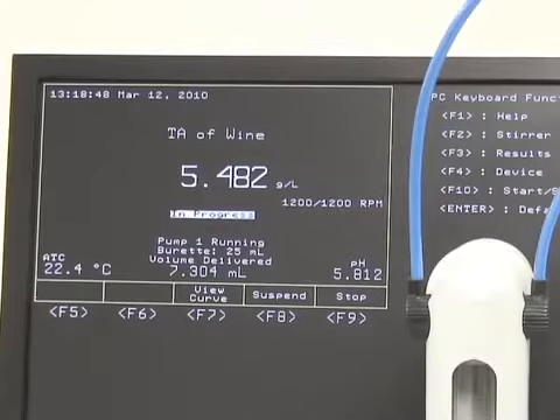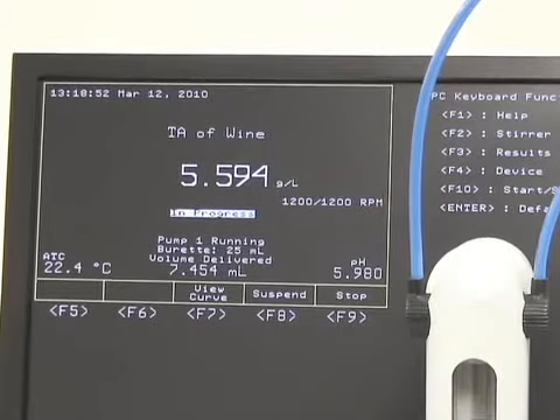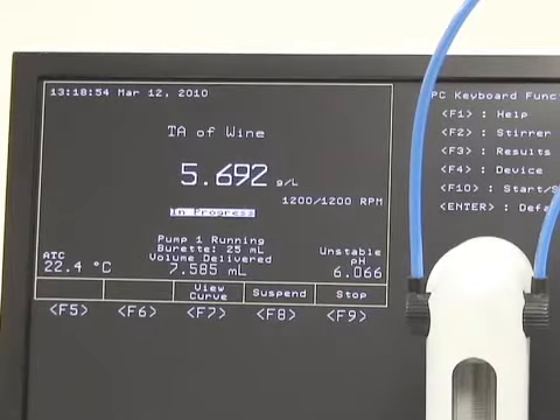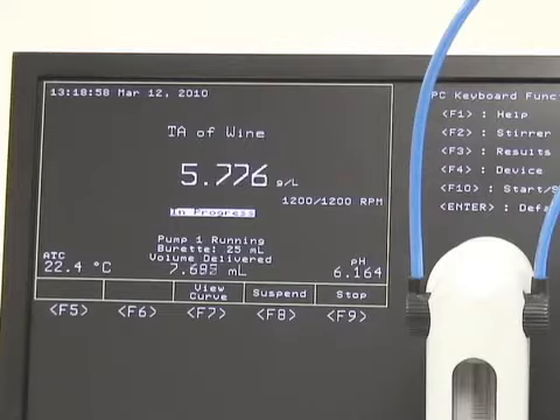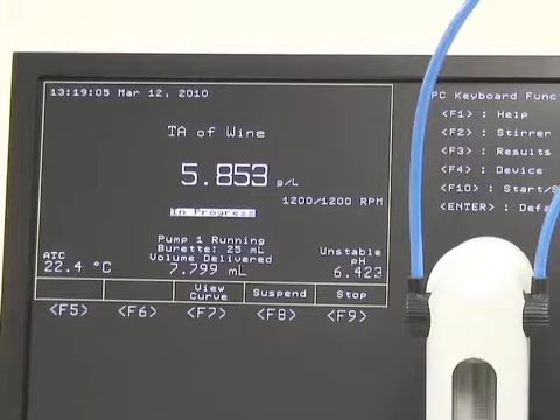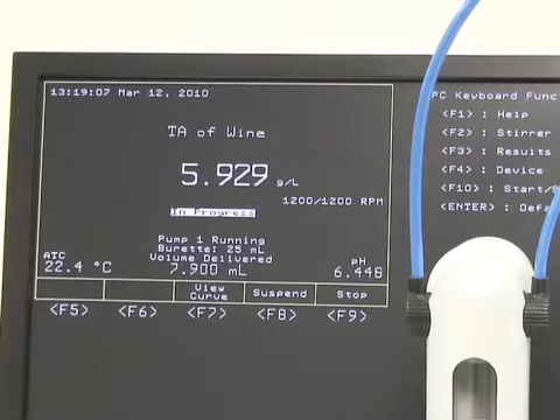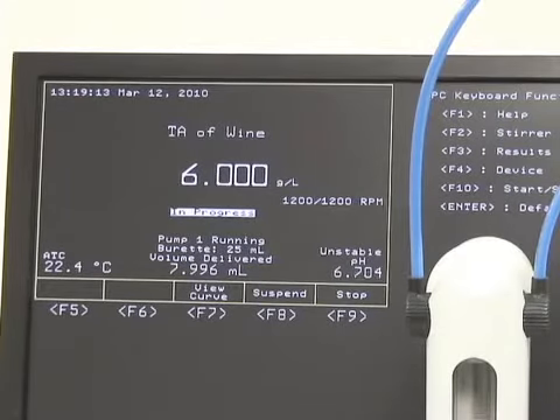All the methods, remember, on the 901 are programmable. If you have higher acids or lower acids, you can set your machine up with higher or lower dosing, higher or lower speeds to get the test a little faster or slow it down for lower total acidity numbers. So we're moving right along. pH keeps rising. We're getting closer and closer to our 8.2 endpoint. The volume should be slowing down here any second once we cross about the 7.0 pH line.